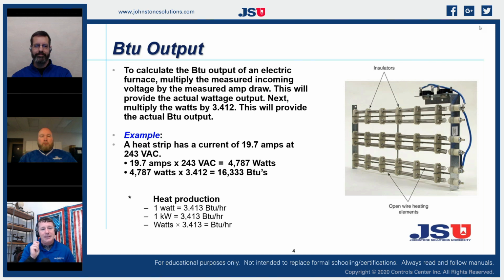That's what we're measuring. Now, if we want to convert that over to BTUs, it's as simple as using a constant of 3.412. So if I take my watts times 3.412, that is my actual BTUs of my heater based on my voltage and my amperage. And that changes. That depends on my voltage, because if I have low voltage, remember, if one number changes, I'm going to go the other direction on one of my other numbers, right? So I can use that to calculate what my actual BTU rating is of that particular element. And I want to do that, and I want to write that down. I want to track the watts of my electric element to see if it is degrading, to see if it is changing its resistance over time.